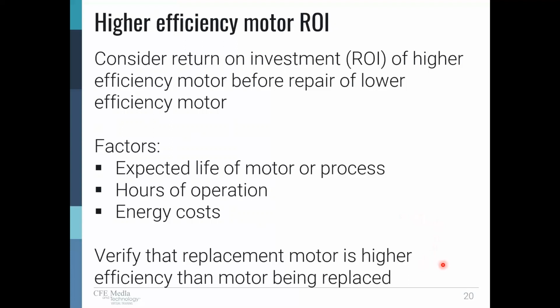And when we get that premium efficiency motor, we go out and get bids on it and look at the pricing. We want to look at the nameplate efficiency of the motors being used as replacements, because one may have a higher nameplate rated efficiency than another. The U.S. Department of Energy regulations give criteria for what the nominal or average efficiency should be for a given power rating and speed. But even within that, the manufacturer can make something even more efficient than the standard requires. And there's a minimum efficiency, so they can be below that nominal or average efficiency and still be acceptable. You can't build every motor as efficiently as you want; there are always going to be variations in production. But if we look at those motors and find one that says it's 95.3% efficient and one that's 94.9, we probably want to go for the 95.3 because we're going to gain 0.4 of a point of efficiency. And if it's going to run 90,000 hours, I'm sure that's going to add up to a lot of money over that period of time.